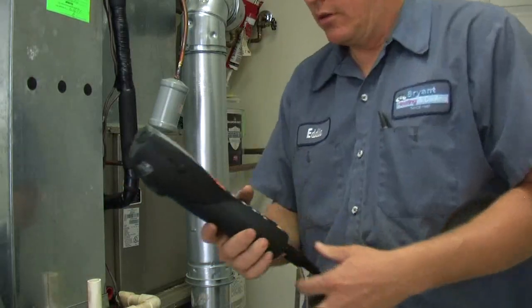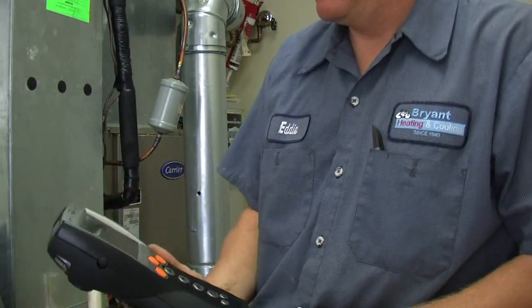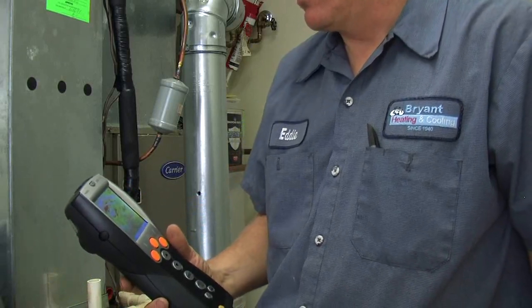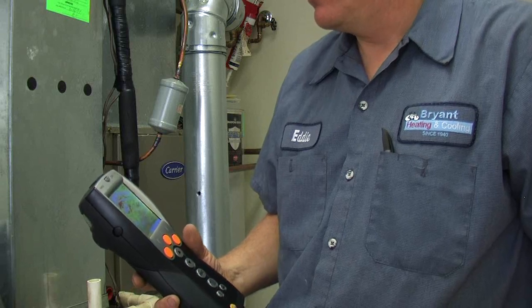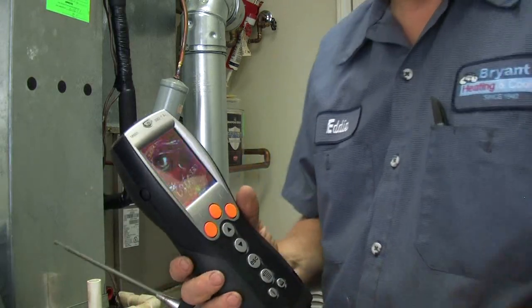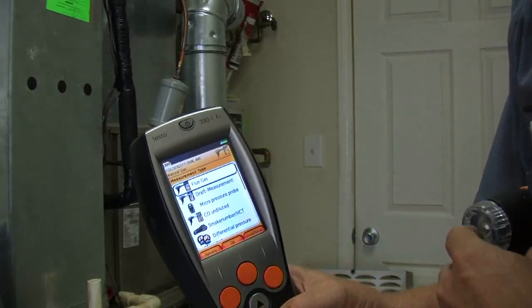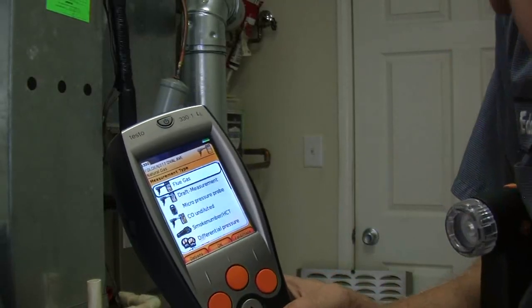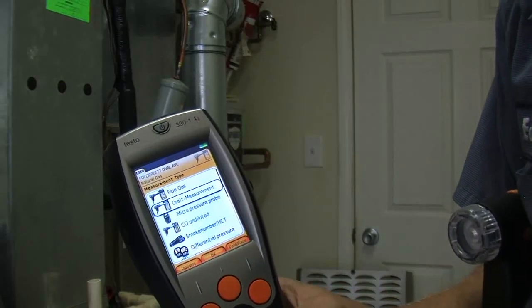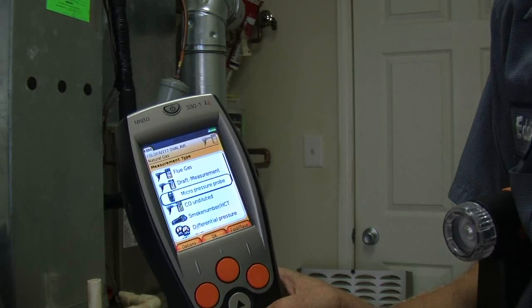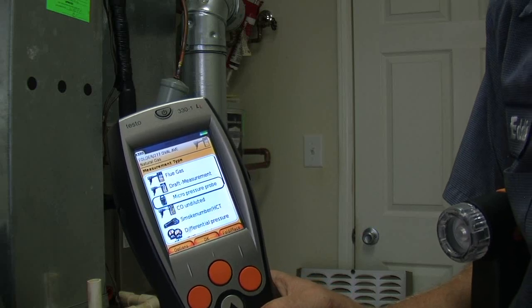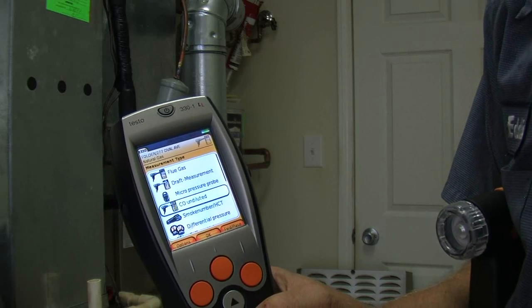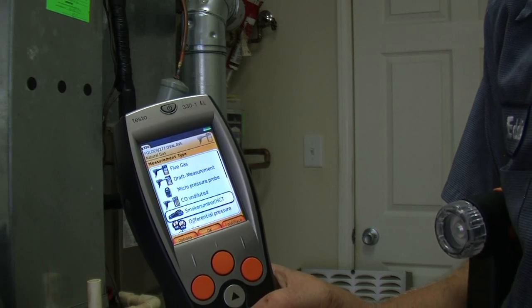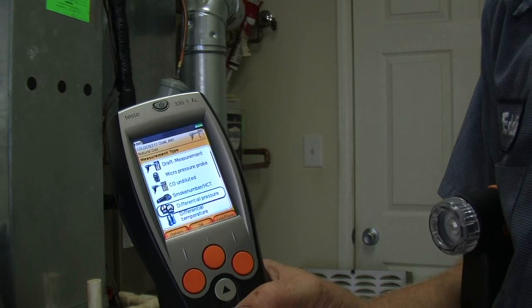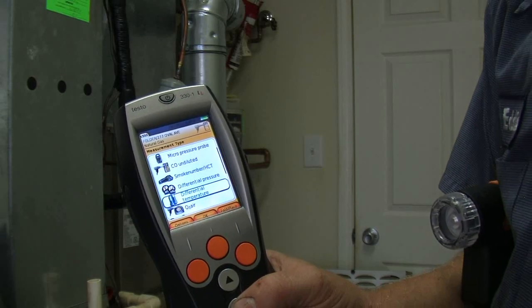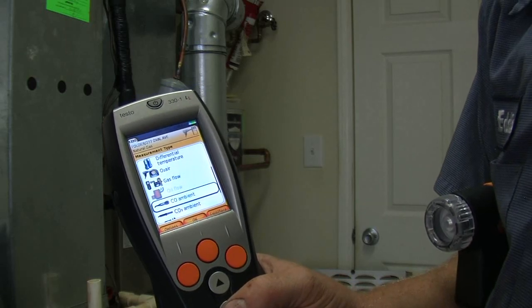Next thing, I'm going to go ahead and turn my meter on. It's got a zero out. It takes it 20 seconds or so to zero, so I'm going to pause the camera while it does that. Then I'll show it to you. Alright, so it's zeroed out. Let me show you this screen here. What the meter will do, it's going to measure flue gas. It'll measure draft. Get a micro pressure probe, that's an accessory you've got to buy. CO undiluted, smoke number, so if you're doing oil furnaces, differential pressure, that's what we're going to use to measure gas pressure. It'll measure differential in temperature, O2 air, gas flow, and it has oil flow.